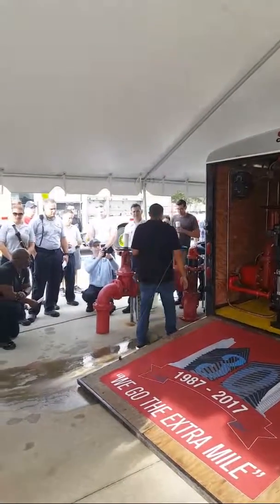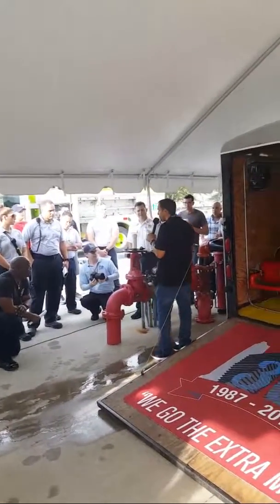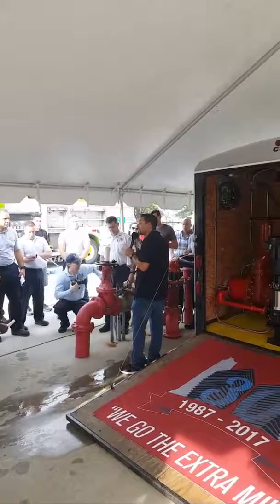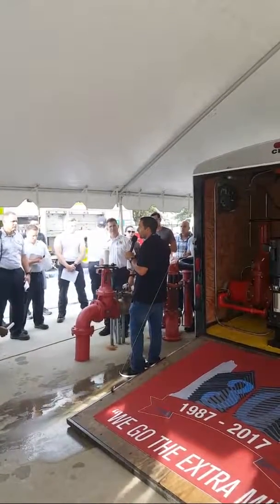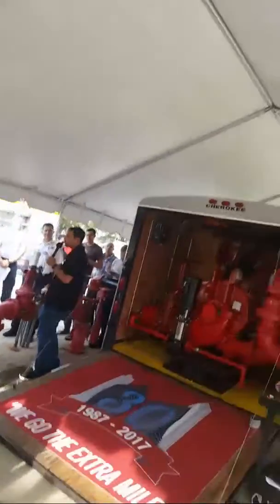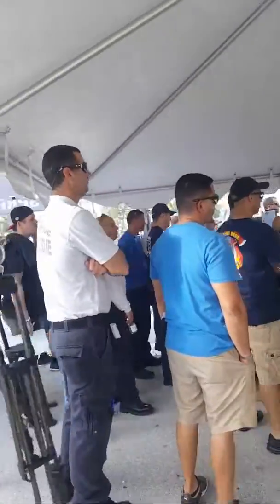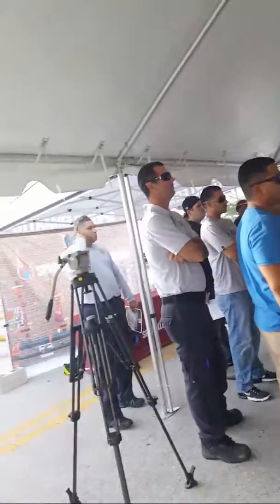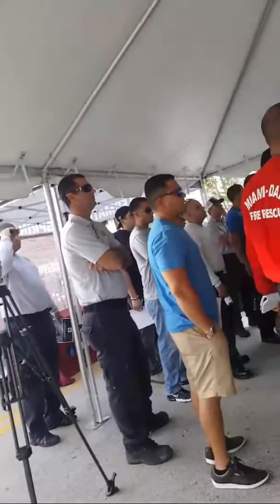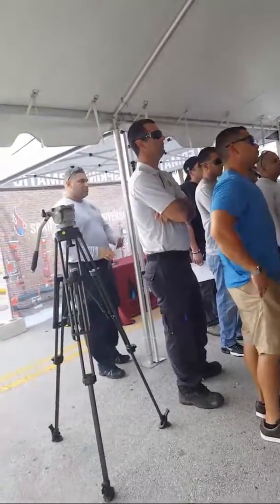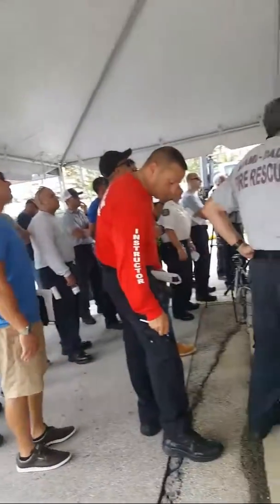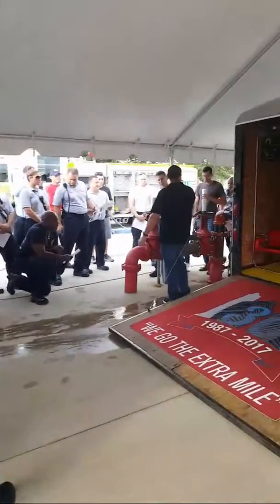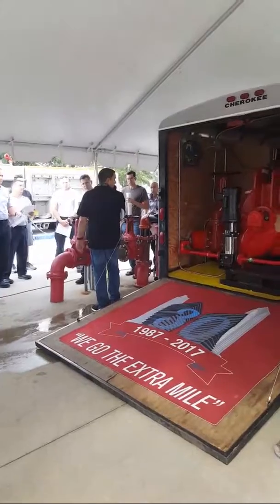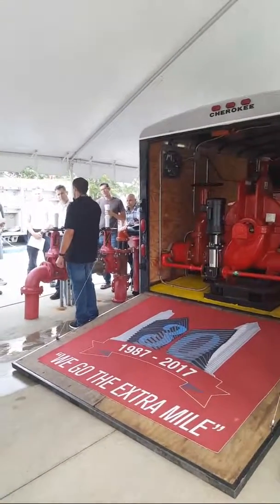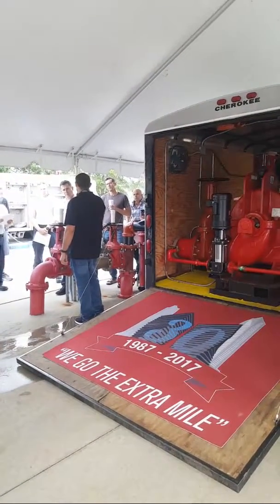No? Okay. Through the backflow, we either go directly into a riser system, or in this case, we go directly to our fire pump. What a fire pump does is take the pressure of the city water and add to it - it adds volume and pressure. In this case, we have a pump doing about 750 gallons a minute.